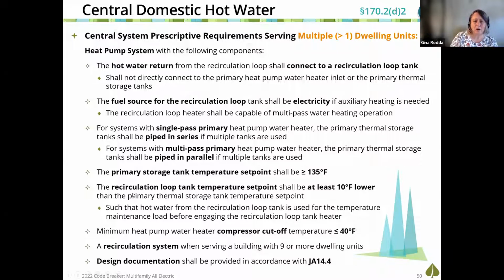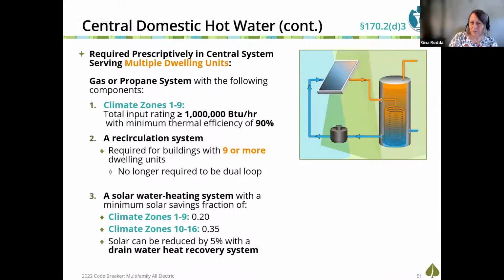The biggest thing to be aware of is the primary storage tank. The storage tank sizes are huge because we're slowly heating up water in a heat pump system, and we need to make sure we have that volume to meet peak load conditions—that volume's pretty beefy. I'm also going to have a great recirculation reheat system because I'm slowly and very energy efficiently heating up water, and I want to make sure it stays at a viable temperature as it's being stored and recirculated around the building to whoever needs to use it.